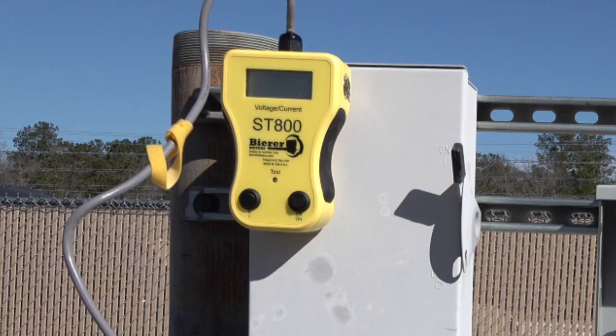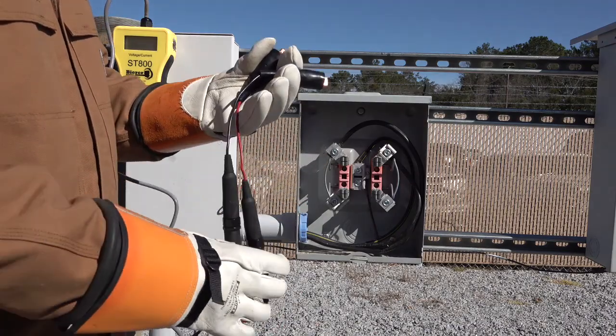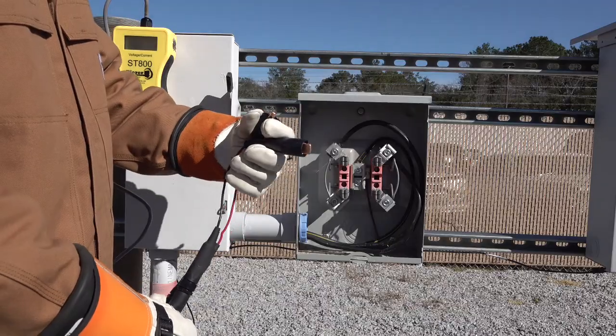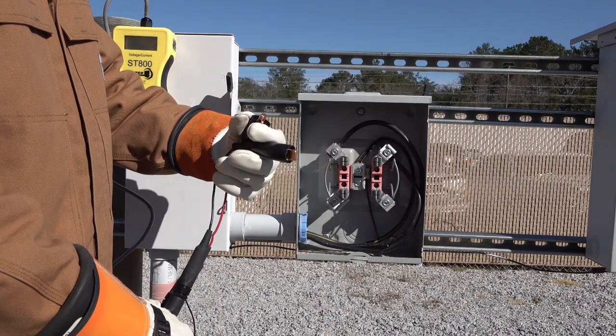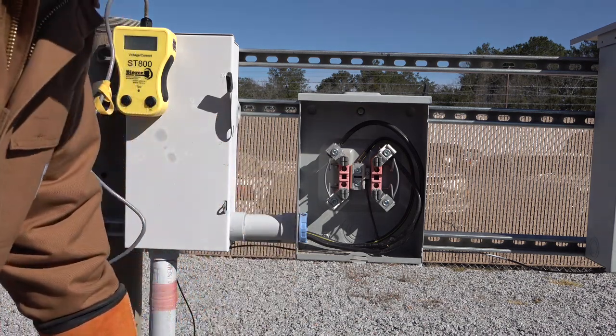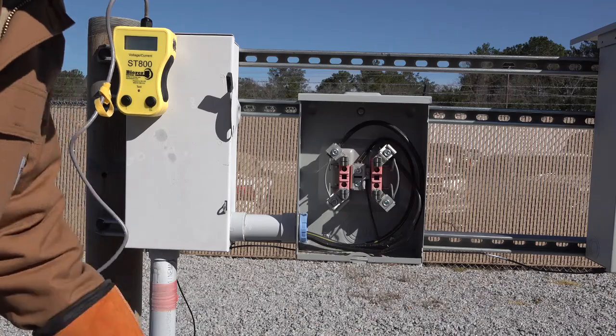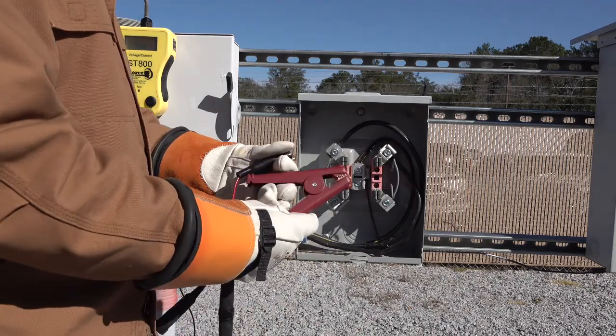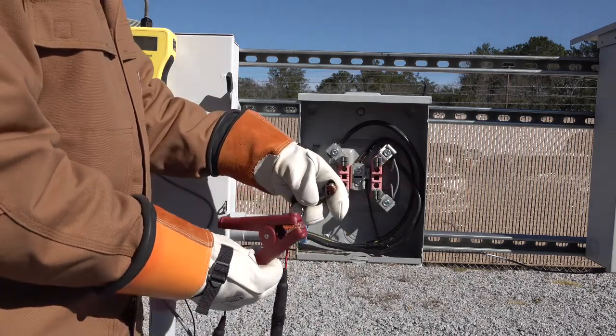There is also a green test light, and this light comes on whenever the unit is in operation or attached to a live circuit. The green light will blink as the unit pulses. The ST800 is available with two different size clamps for connection. The small connectors, as seen here, work better for small meter bases or areas with limited space. We also have available, upon request, a larger, more durable insulated clamp.